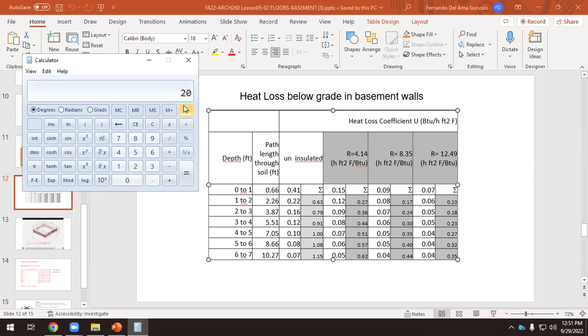And how can we get 12? If we have 4 inches divided by 0.2, this is 20. So basically these columns mean that here we have 1 inch of thermal insulation, 2 inches, and 4 inches of thermal insulation. But even 4 inches is something ridiculous nowadays. We're talking about 10 or 12 inches of thermal insulation, and the R value that we are targeting is around 40 or 50. So those values are a little outdated, but I'm sure that in a new version of ARCH260 they will change those values.